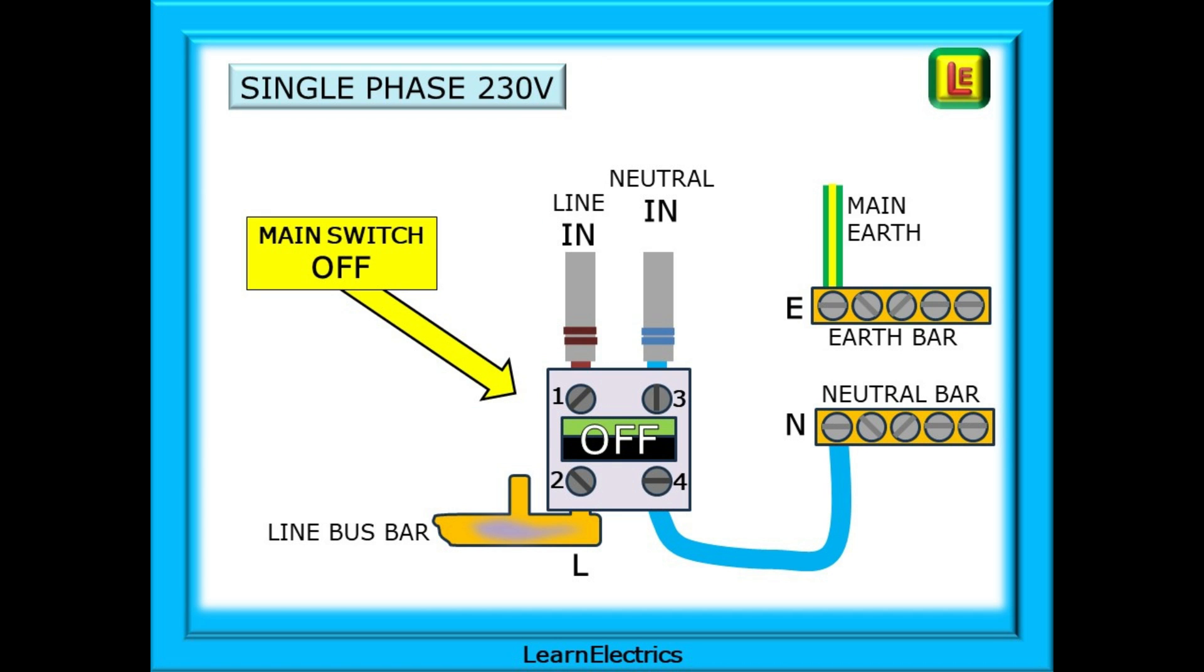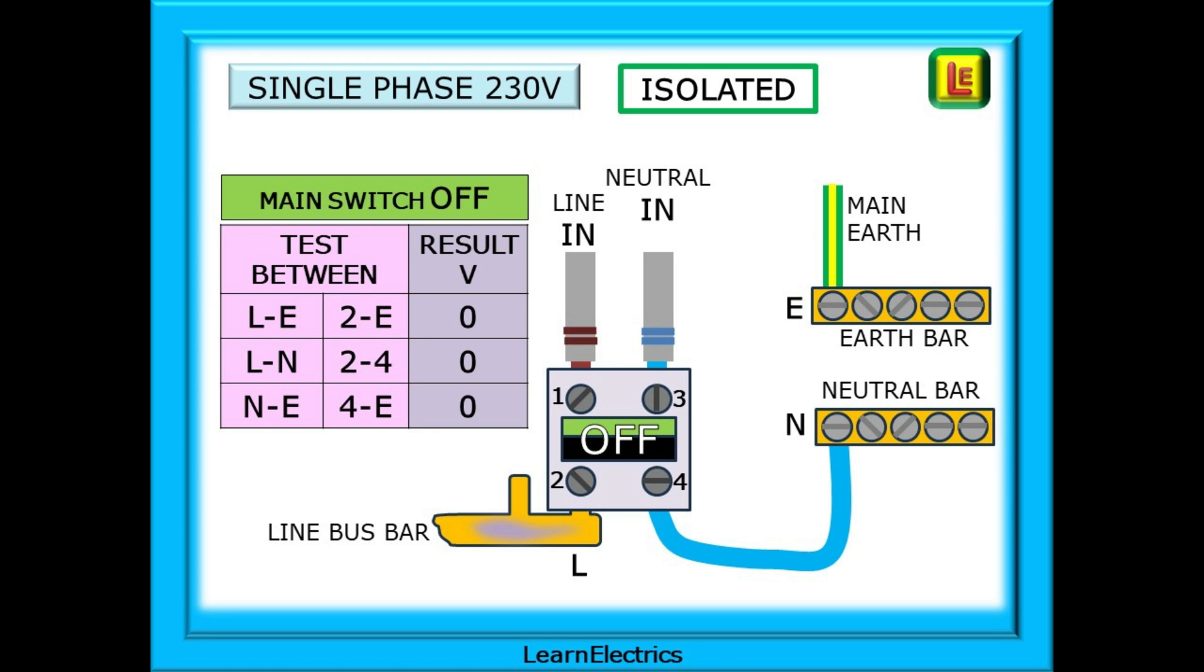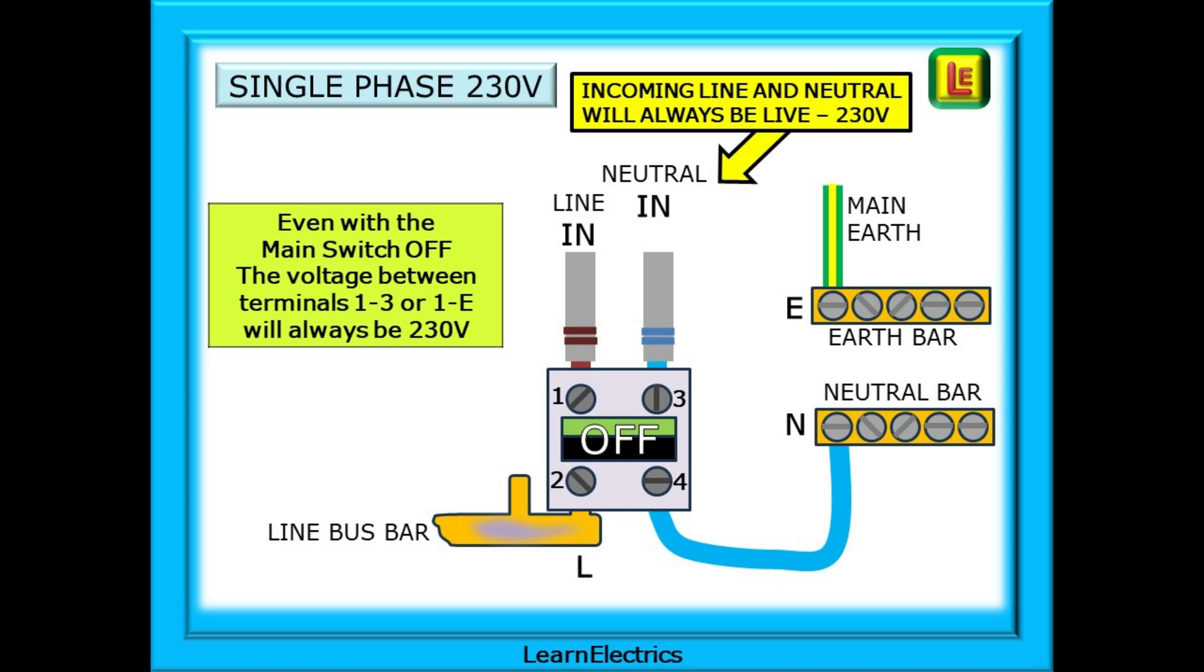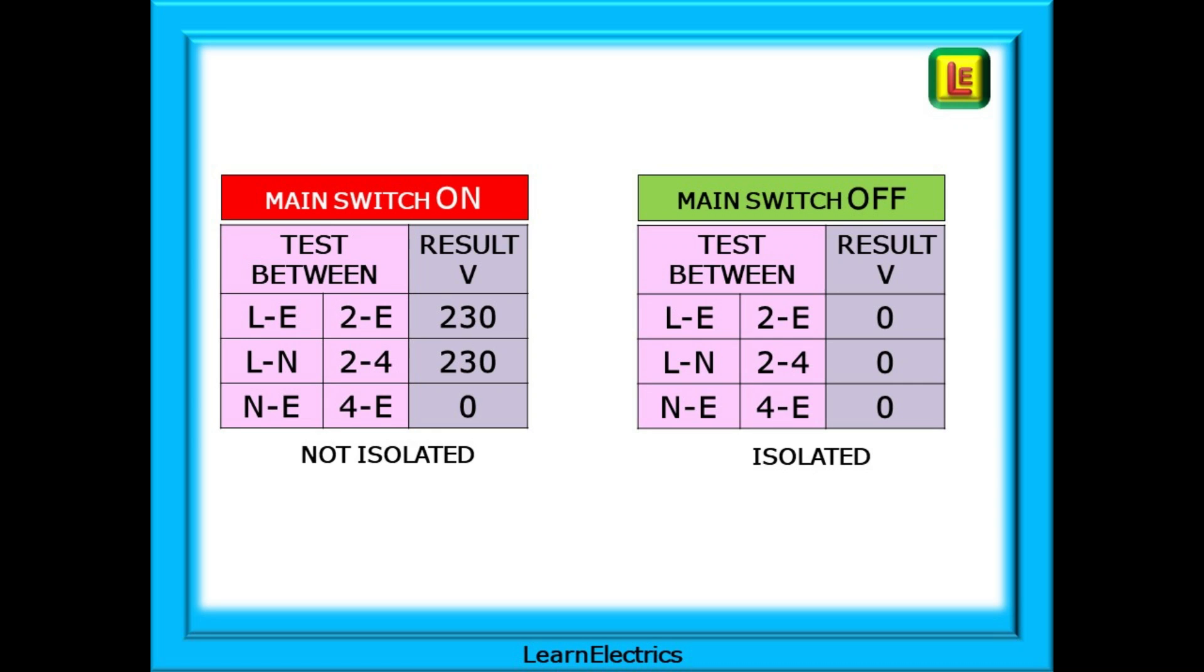Now we can turn the main switch off and isolate the installation. The intention of safe isolation is to remove the installation from all sources of electrical energy. With the main switch off, we want to prove isolation, so carry out the voltage checks again. What should we expect? Line to earth is zero. Line to neutral is zero. And neutral to earth is also zero. All three possible combinations are zero volts. The installation is isolated. The installation after the main switch is isolated, but the top half of the switch is still live. The incoming main tails are still live unless the cutout fuse has been removed. Although the installation is dead, there is still live electricity at certain points inside the consumer unit. And these two tables should act as a refresher of the voltages to be expected when comparing an installation that is not isolated to one that is isolated.